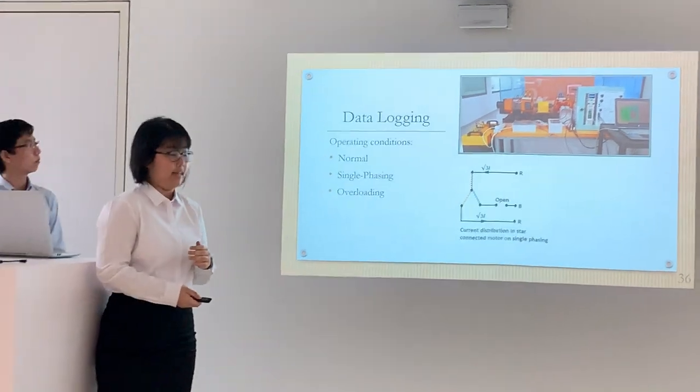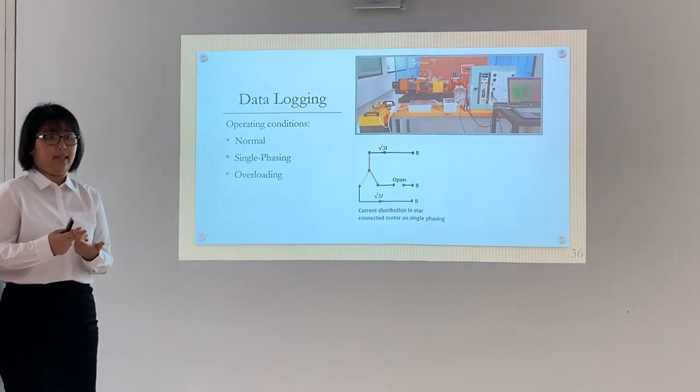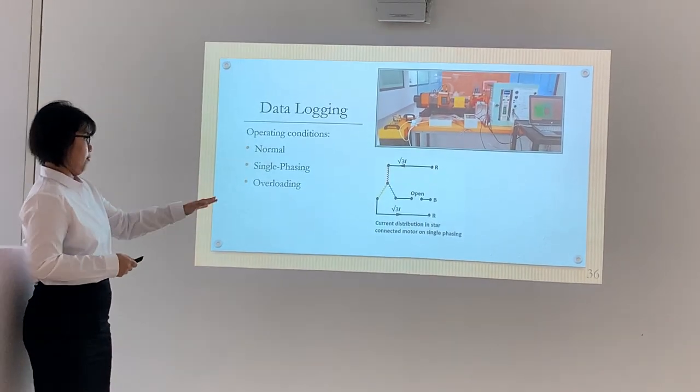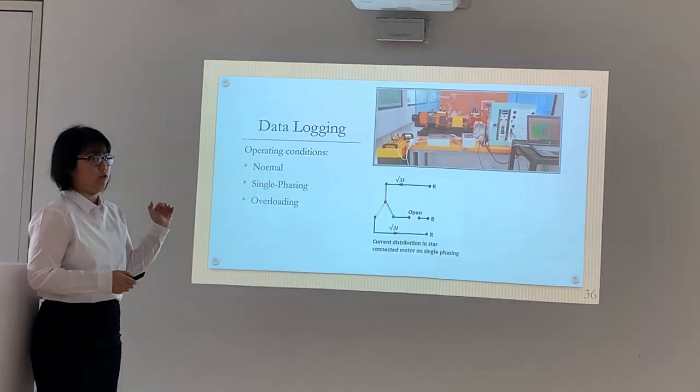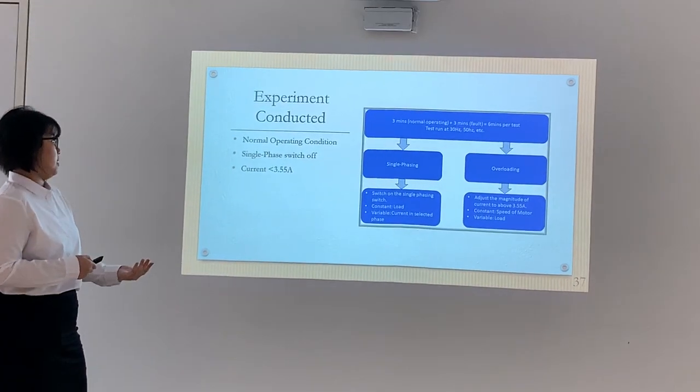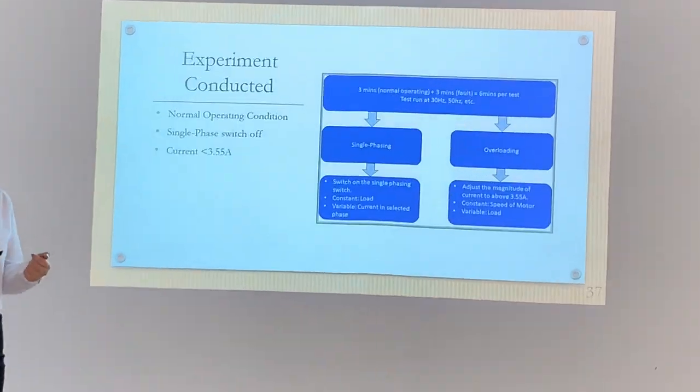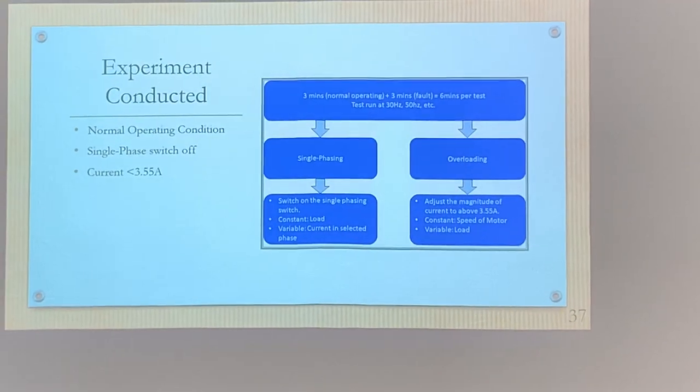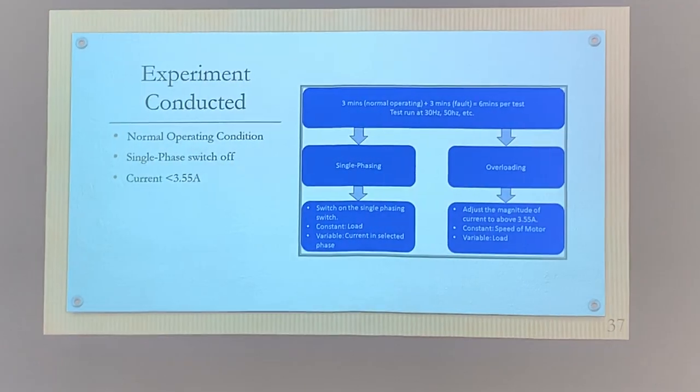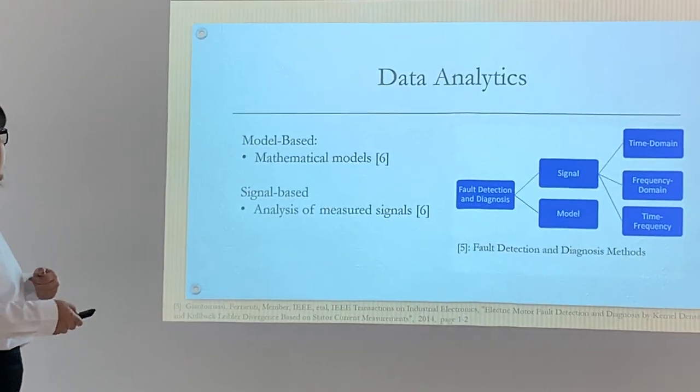I'll be talking about data logging and analysis. We take readings in three conditions: normal, single phasing, and overloading conditions. The last two are fault conditions. For single phasing, this diagram shows that in one of the phases there is no current going through, which is an open circuit. For the single phasing test, the constant is the load and the variable is the current in the selected phase. In the overloading test, the current will be adjusted above 3.5 amperes. The constant is the speed of the motor and the variable is the load.